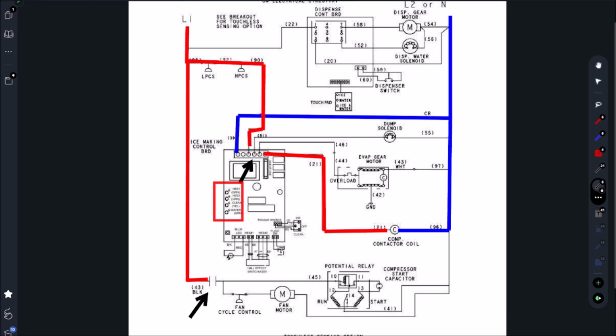There's no time to go around the machine and check for power. So I was fully prepared for that, and I knew I had to test for power here. So how I confirm that these contacts are closing right here is I tested for power right here. You saw in the video there, I got 120 volts right on this terminal here. So that's telling me this contactor contact is good.